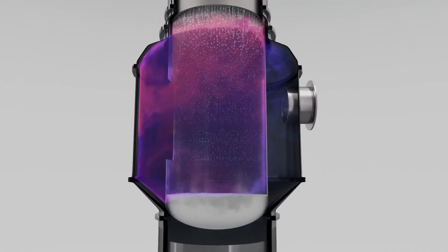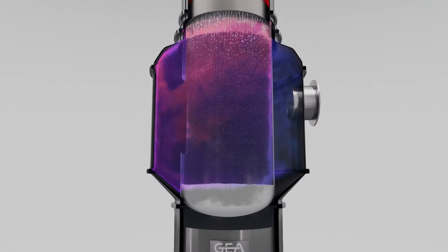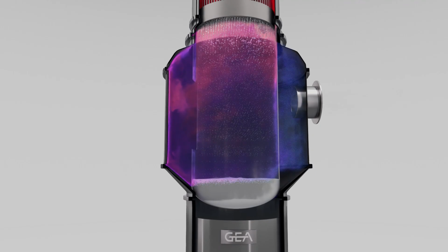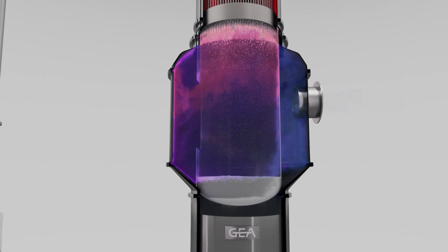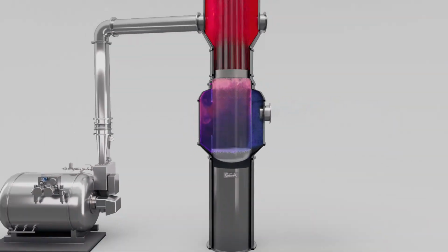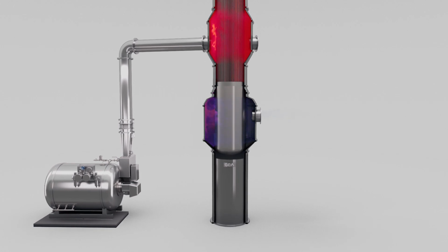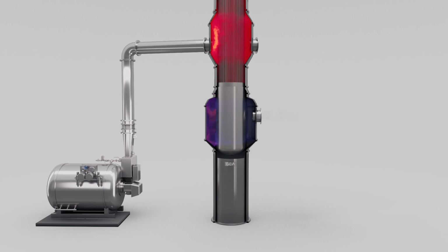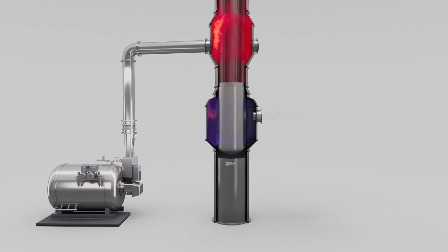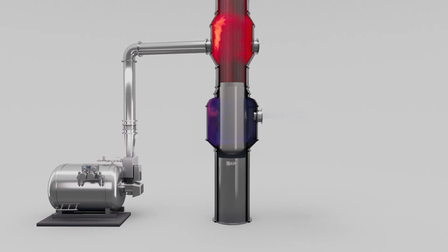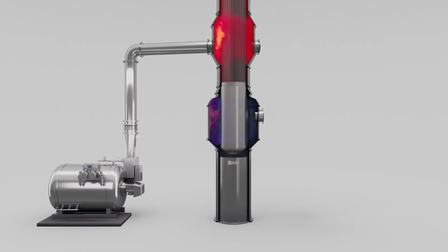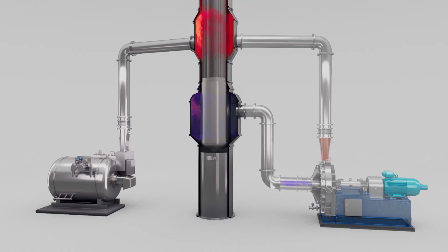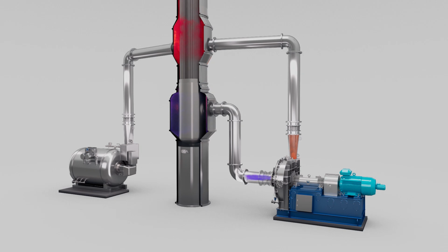Water vapor that is at a lower temperature than the heating steam fed to the system is left behind. In the conventional evaporation process, the heating steam is generated in a steam boiler. This is an energy-intensive process because as the water is transformed into vapor, it absorbs a high amount of energy and has to be brought up to the required temperature as well. How can we increase the temperature of the existing vapor so that it can be reused? By using the fans for mechanical vapor recompression from TLT-Turbo.